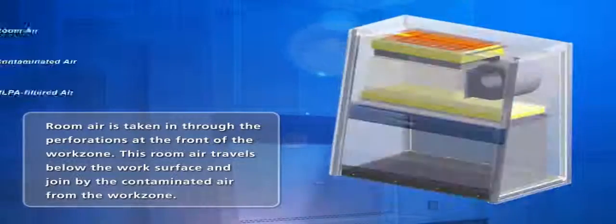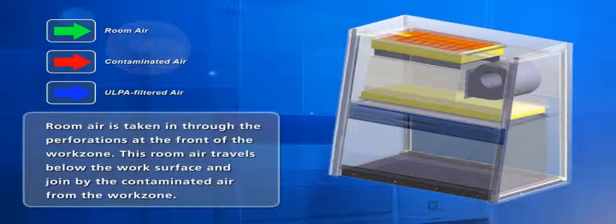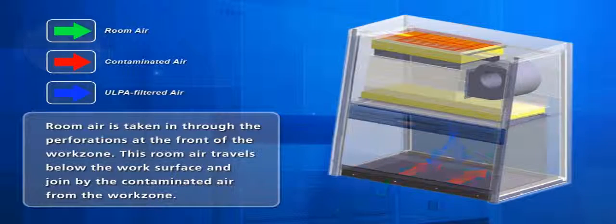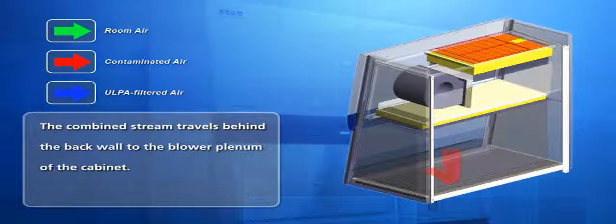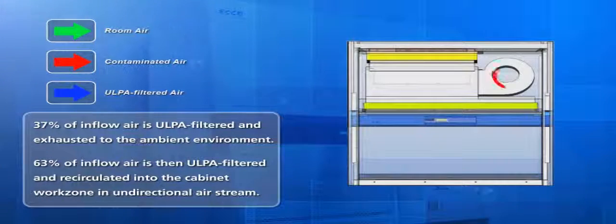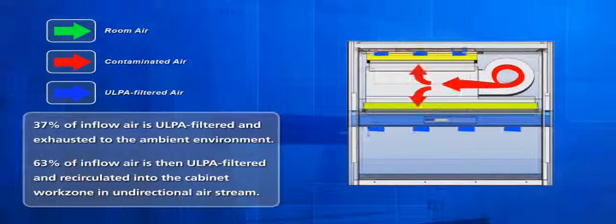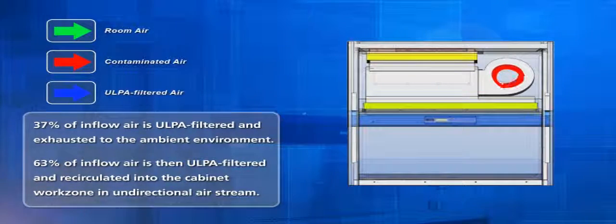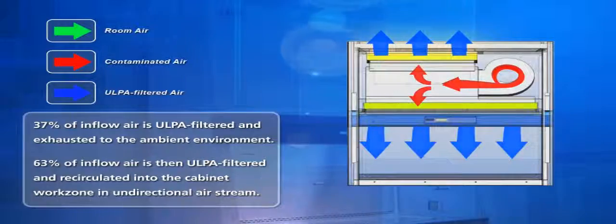A Class II Type A2 is a recirculating design biosafety cabinet. This means that room air is drawn into the cabinet through the front air grills and travels below the work surface through the back cabinet and into the blower plenum. From the blower, the air passes through the ULPA filters. Approximately 37% of the air is ULPA filtered and exhausted to the surrounding environment. The remaining 63% of the air is ULPA filtered and recirculated back into the cabinet work zone as unidirectional or laminar downflow air, providing a sterile and non-turbulent work zone environment.